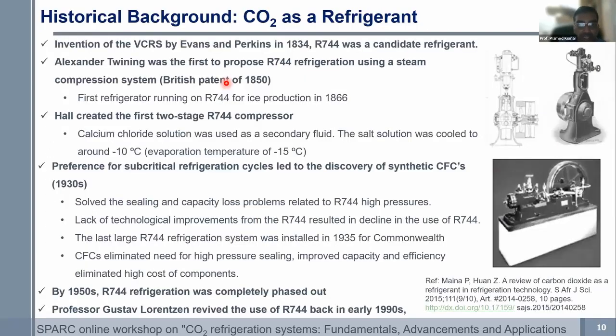Okay. So historically, if you look at it, carbon dioxide was used before this chemical evolution in the early 20th century, where there was a lot of emphasis on creating new chemicals and synthesis. Before that, there were probably only two very good refrigerants, ammonia and carbon dioxide, that were widely used. There were a lot of attempts made to build compressors for carbon dioxide and ammonia. Carbon dioxide being a high pressure refrigerant, there were a lot of leakages. So the system did have its own set of issues in the early stages of the industrial world. But then slowly, with the advent of synthetic refrigerants, carbon dioxide was just written down in history.